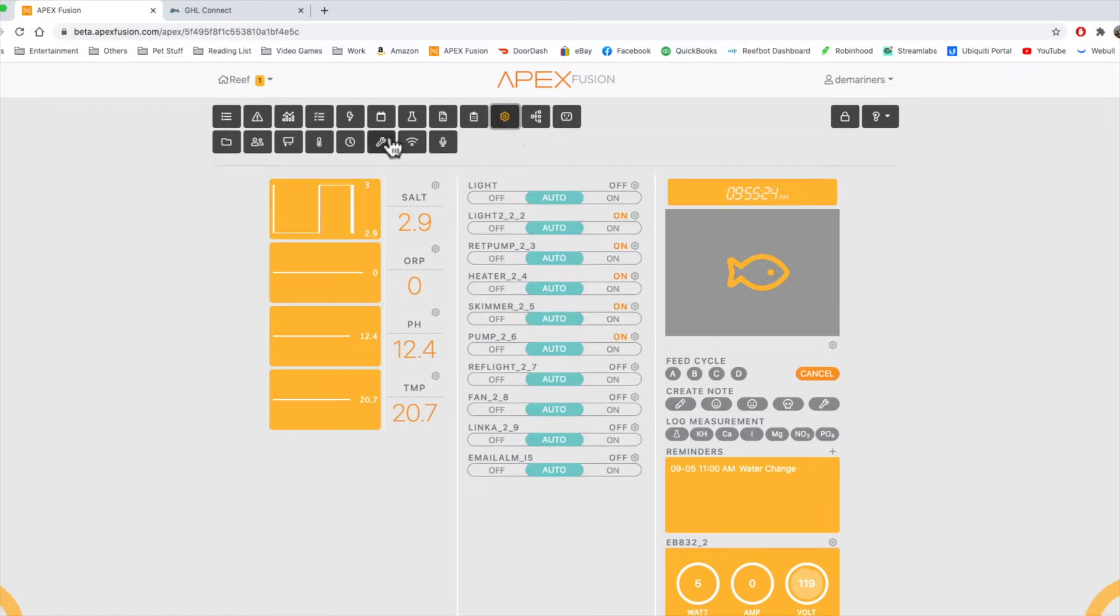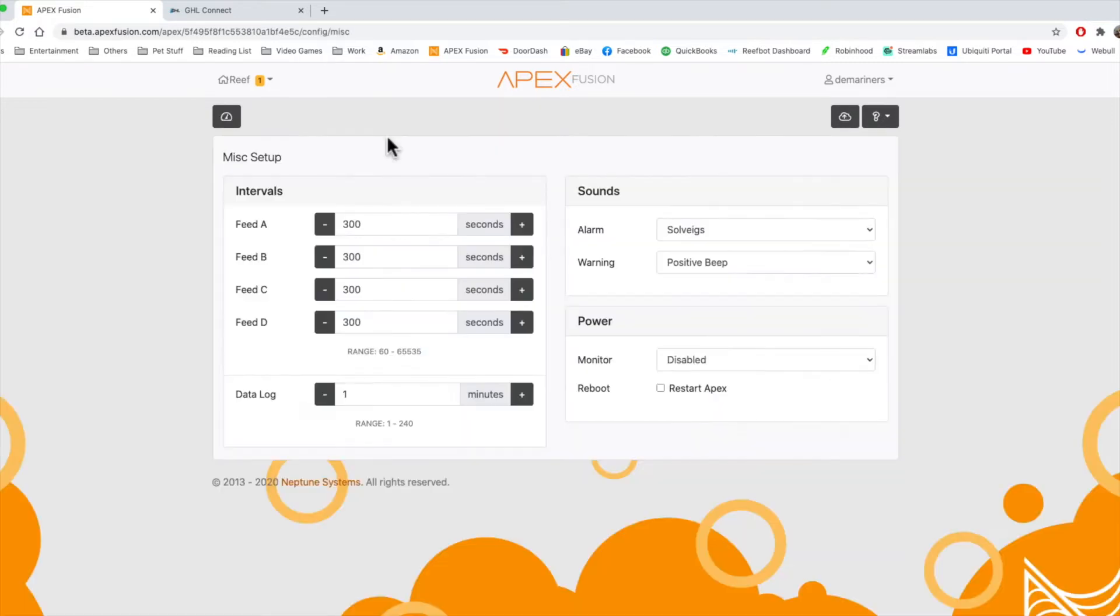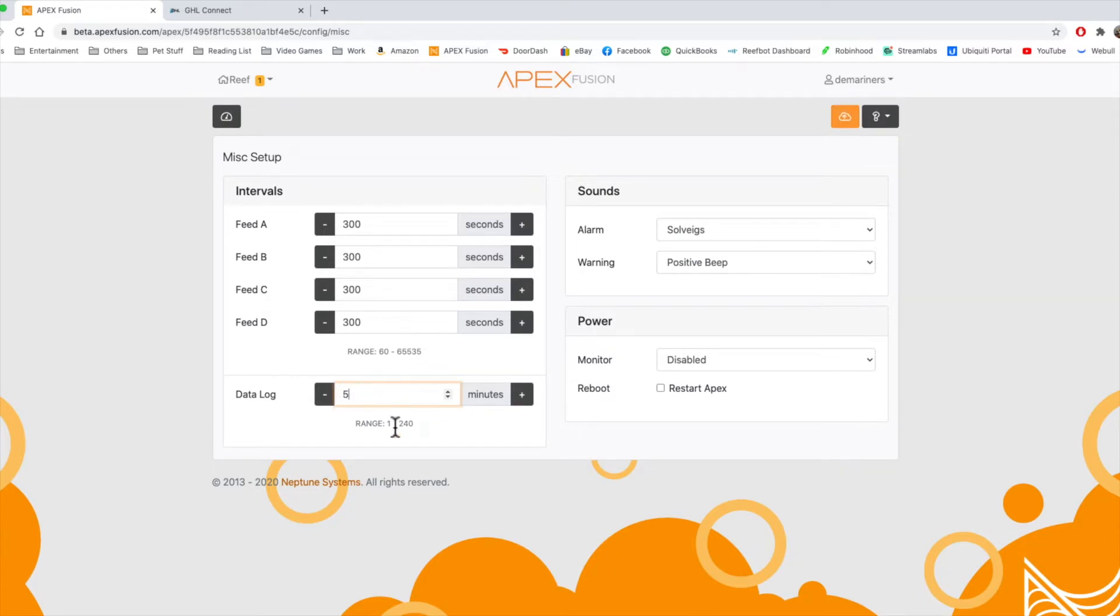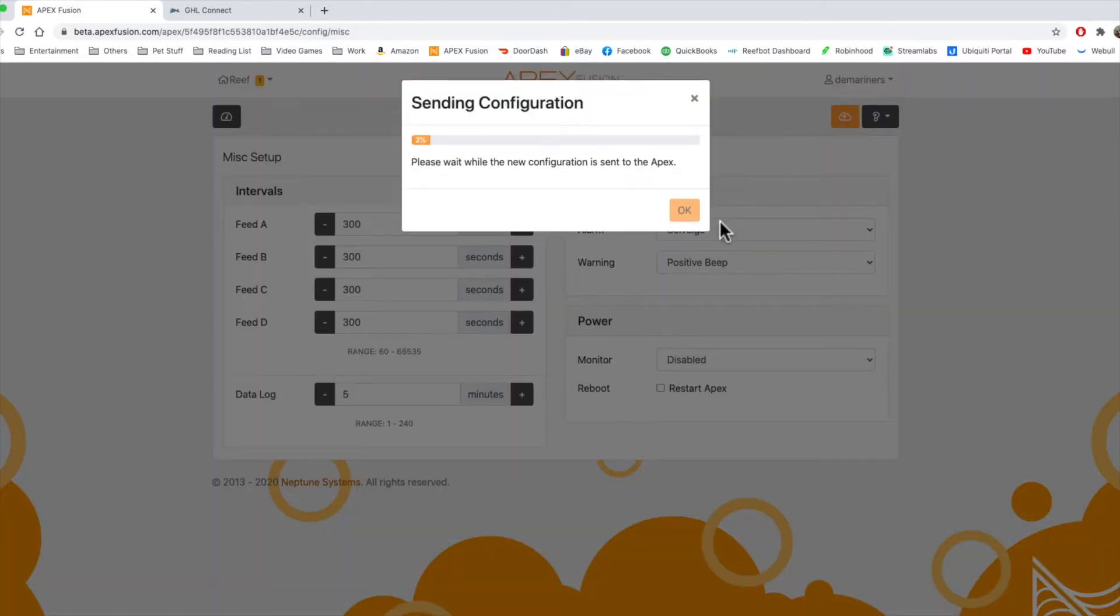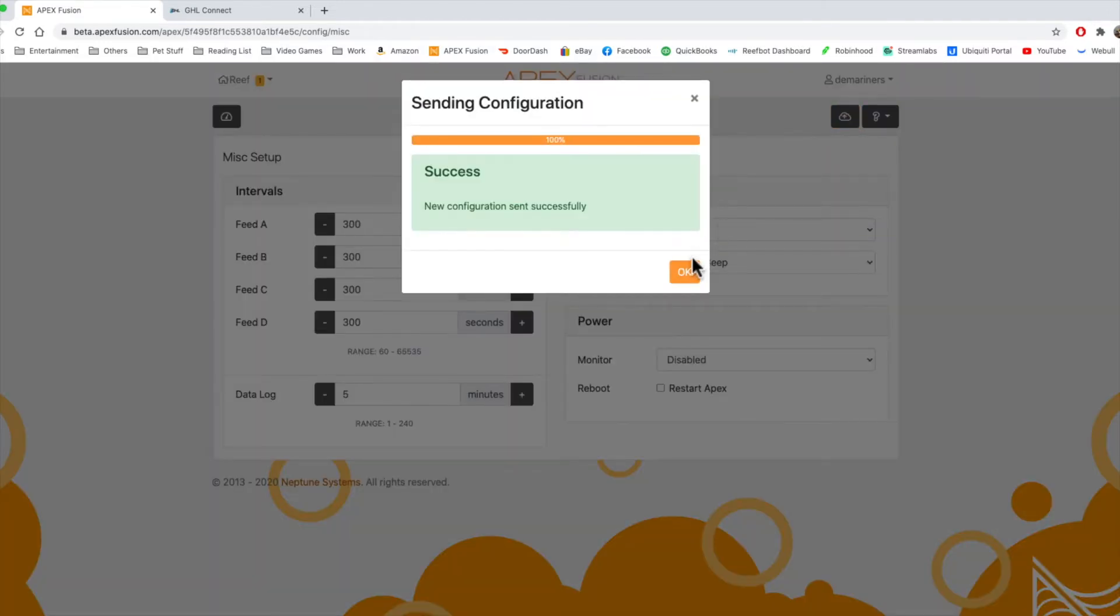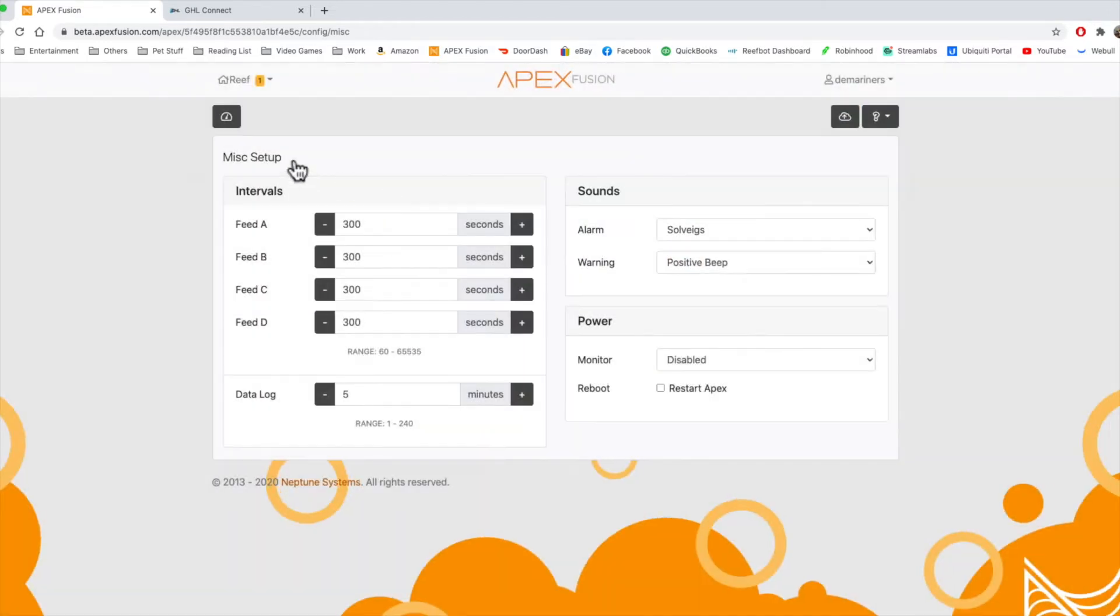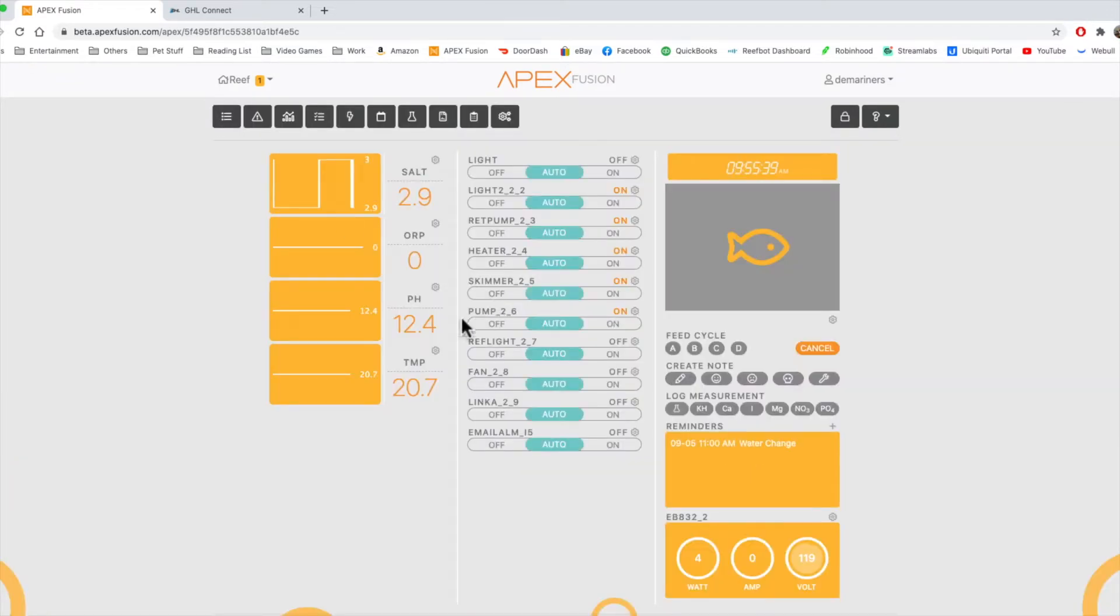So if we go to the miscellaneous setup, and we have a data log of one minute, it's going to get a data log of one minute. The recommendation has always been about five minutes because that data is going to get quite large and can actually slow down the system when you're connecting to the cloud. So I suggest putting that to about five minutes.